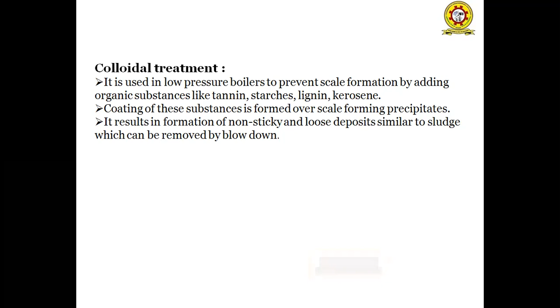Next one is the colloidal method. It is used for low pressure boilers to prevent scale formation by adding substances like tannin, starches, lignin, and kerosene. A coating of these substances is formed over the scale-forming precipitates. It results in the formation of non-sticky and loose deposits, similar to sludge, which can be removed by the blow down treatment. So this is the blow down treatment.